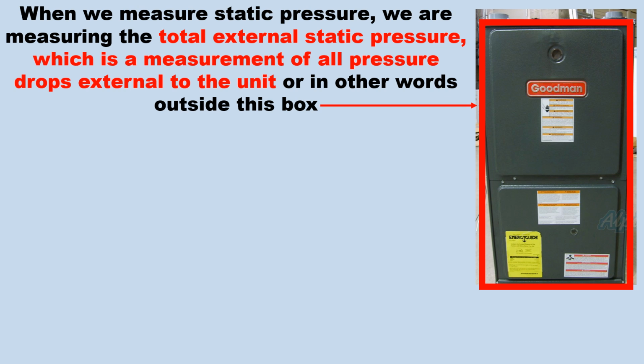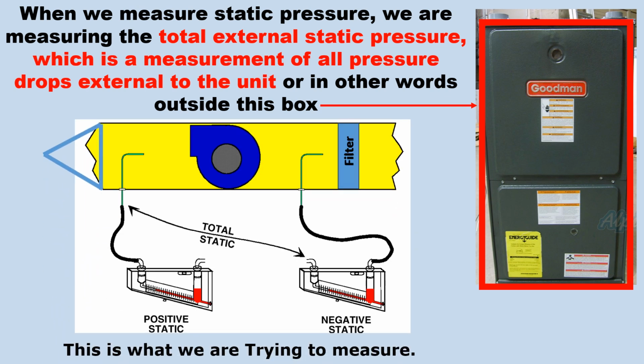When we measure static pressure, we are measuring the total external static pressure, which is a measurement of all pressure drops external to the unit, or in other words, outside this box. This is what we are trying to measure. All pressure drops within the unit, like the secondary and primary heat exchanger, are not included because they have been accounted for in the design of the air handler or furnace and are not external to the air handler or furnace.